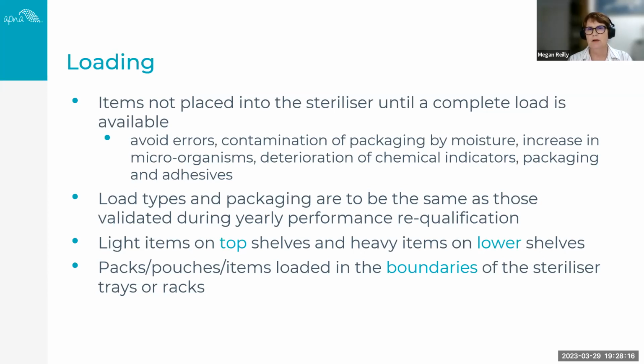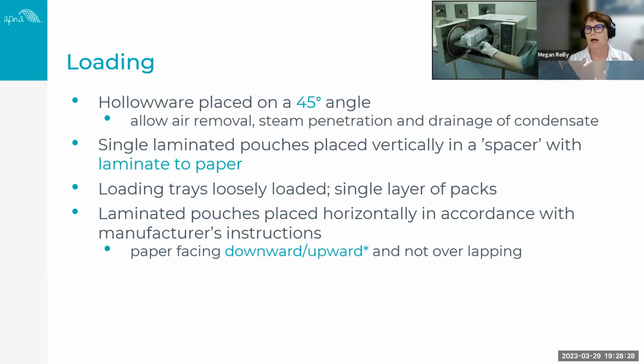So please refer to your steriliser manufacturer's instructions, because they will provide you some guidance or some rules around how best to load your particular steriliser. Certainly if you're using hollowware, we like to have it placed on an angle, and that actually allows the condensation or any water vapour to drain, but it also allows for that air removal and the steam penetration. If you're using single laminated pouches, they can be placed vertically in a spacer, but it must be laminate to paper. Your loading trays, if you're loading horizontally, then it should be just a single layer of packs. They shouldn't be overlaying one another.